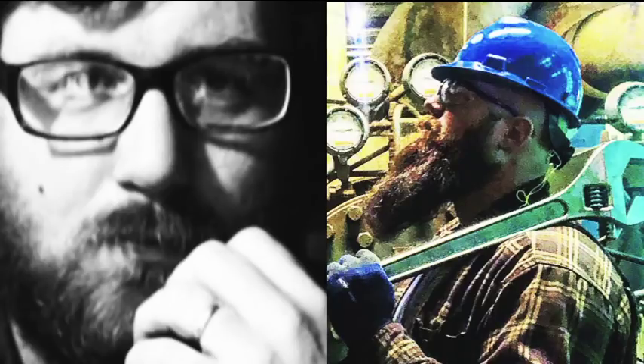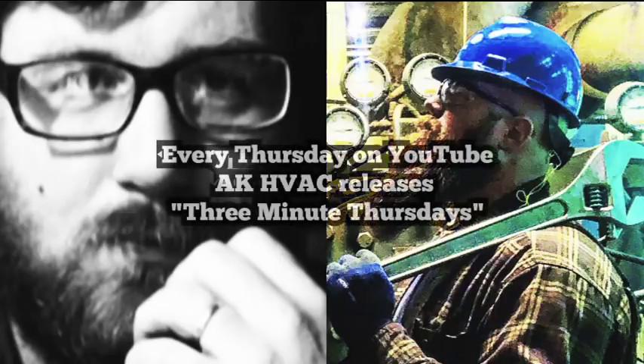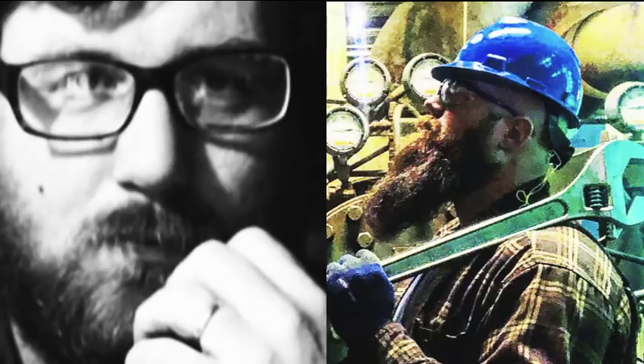So later on, though, about 1 o'clock in the afternoon, dispatch called me and sent me back. They said they had water spilling out of the ceiling in several points of the building. I was a little concerned. I knew it didn't have anything directly to do with what I did. I headed back, and as soon as I got back, the lady came up to me and told me that they had several leaks in the building, and it was on the hot water side. She then informed me that she didn't expect me to have known this, but in that building, they run the boilers 365 days a year. They prefer, if the chiller is going to be looked at, they want the boilers shut down so that the building doesn't get too warm. Well, they didn't tell me that, and they had shut the machines off. So when I left, I never turned the boilers back on because I didn't know they were off. Basically, they came in the next morning, they turned the boilers back on, and we had a bunch of leaks. That's what I was dealing with when I showed up.